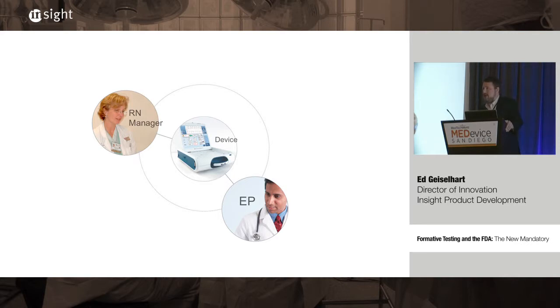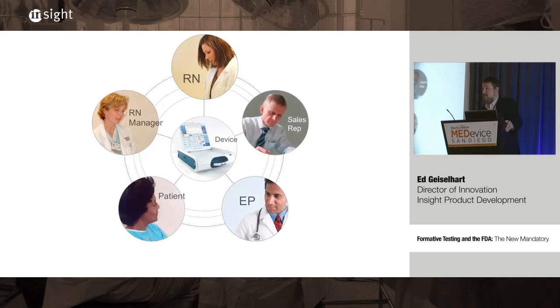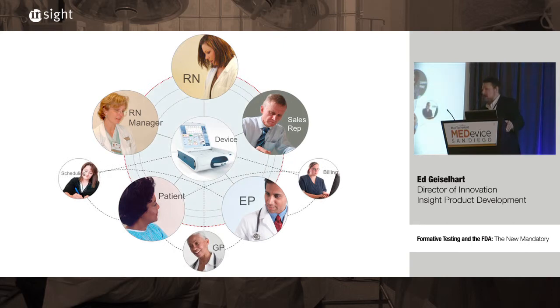And you want to make sure you're not just talking to your expert nurse users, because there will be novice users or inexperienced users or first-time users who will also be interacting with your device. And this is all a component of understanding what is going to happen once your device has been commercialized, in the context of defining potential errors and mitigating them through your device design. So in general, we recommend liberally defining who your user population are to solicit those points of view and those inputs in developing your user risk mitigation strategy.